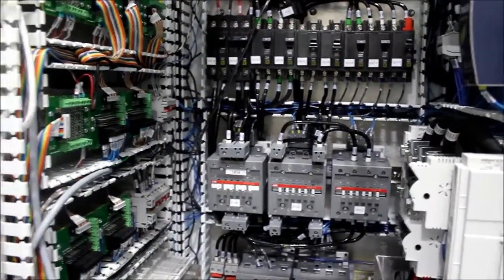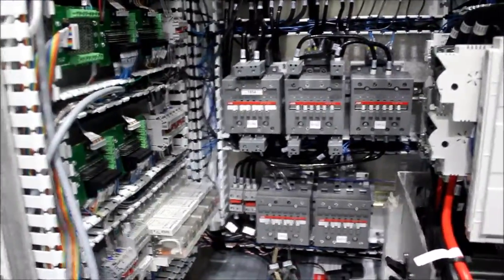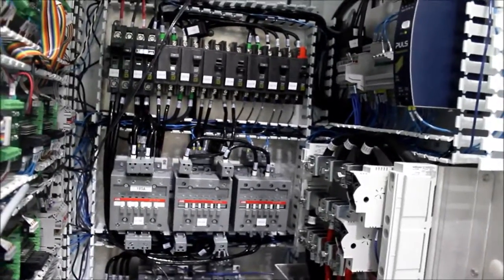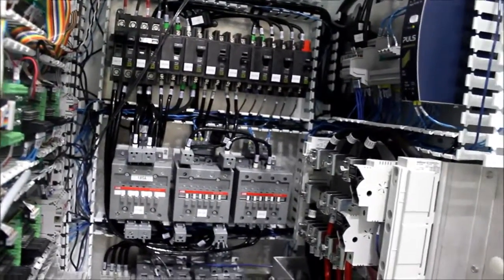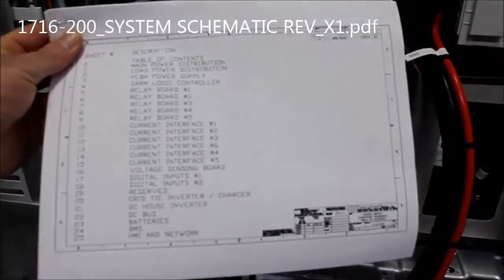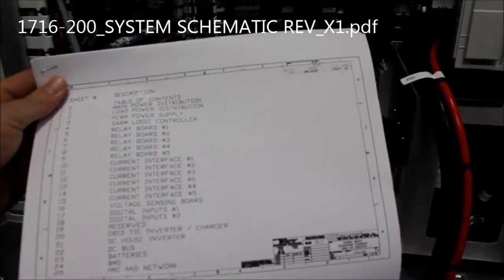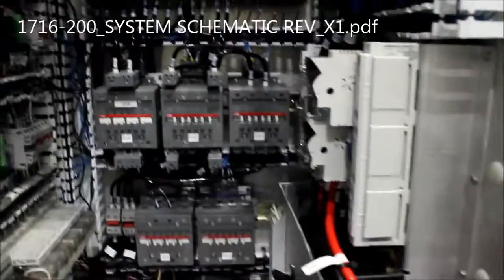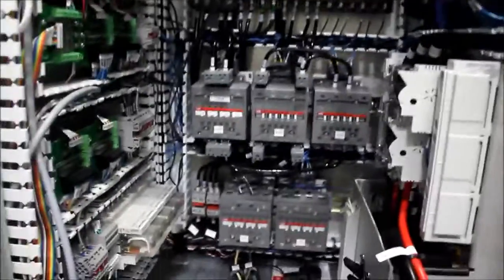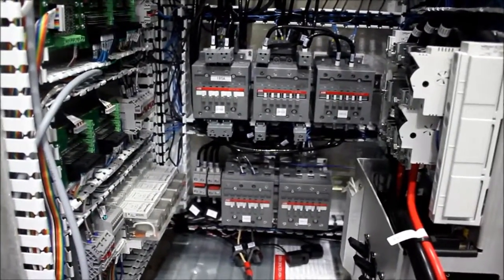This series of circuit breakers and contactors and current protection devices, as well as this side on the inside of the module, is covered in the system wiring diagram PDFs. It is a series of 25 pages or so that covers all of the wiring between devices inside of the energy switch and shows external connections available.